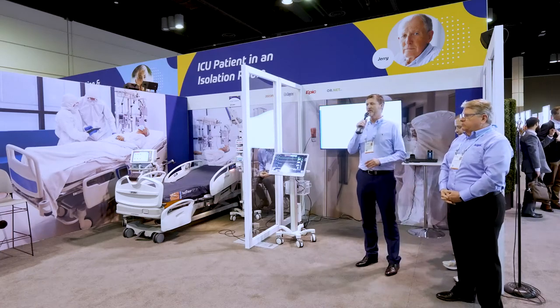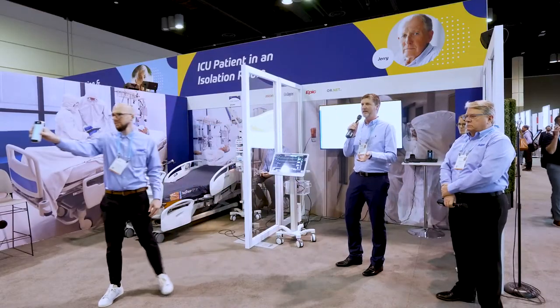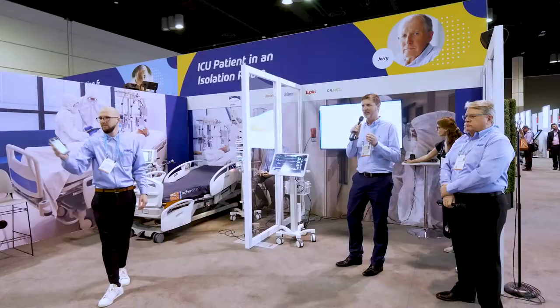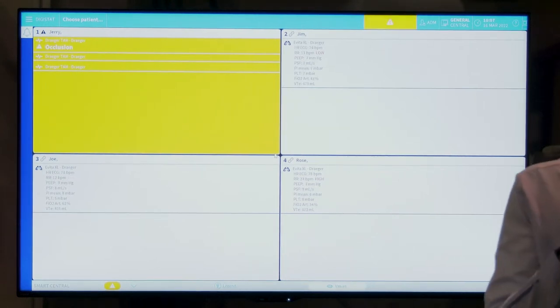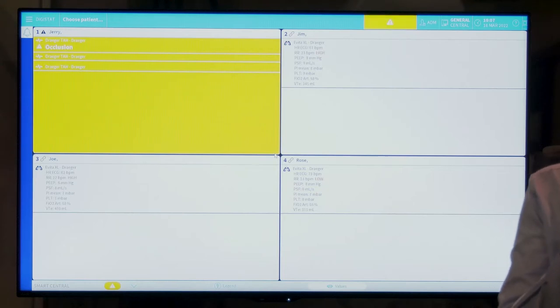Hi, I'm Andy and I'm here to talk about the infusion pumps. The caregiver has gone to prepare medication as indicated by the point-of-care device. The next event is an alarm on the pumps. Historically, the caregiver would have to don PPE, enter the isolation room to find out what was wrong, then possibly exit again to get more medication. Now, the pump alarm is immediately displayed on the caregiver's handheld, showing which drug is involved so they can assess urgency. This information is also displayed at the central nurses' station. In this case, it's an occlusion alarm on a critical drug, requiring an urgent response.